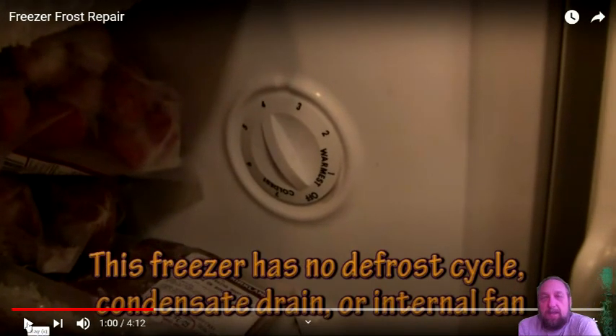All right. He's looking for a defrost cycle in this unit. And a defrost cycle would not build up that much ice towards the front of the door. It would all be wrapped around the evaporator. And on these types of units, the evaporator is at the back, in the very bottom back of the freezer. So you would not have seen ice build up at the top of the unit, especially all over the shelves, unless it's what we call a shelf evaporator. And I'll show you one of those in a minute.